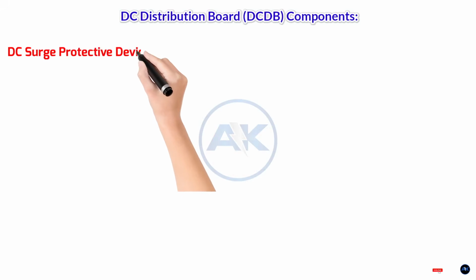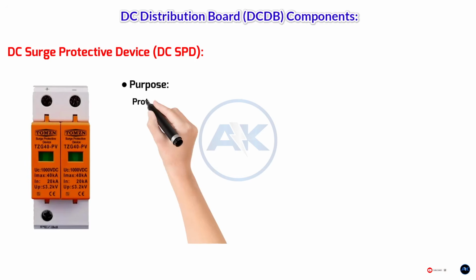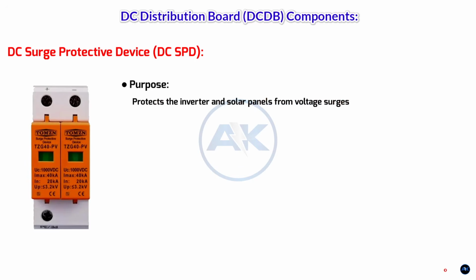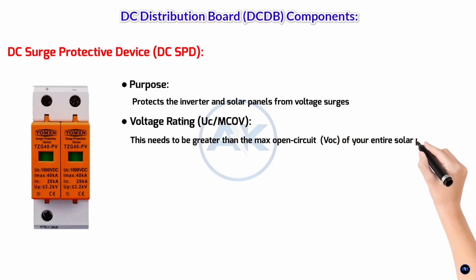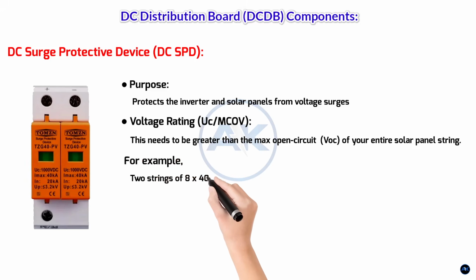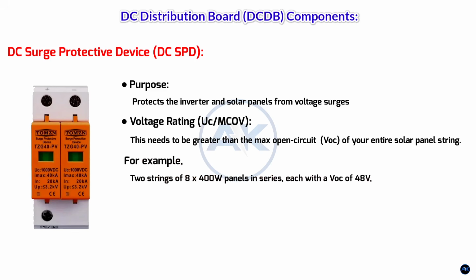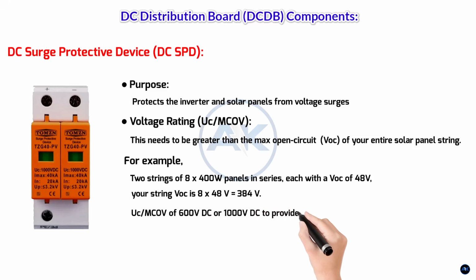DC surge protective device, DC SPD, purpose: protects the inverter and solar panels from voltage surges caused by lightning strikes or other electrical disturbances. Voltage rating, UC/MCOV. This needs to be greater than the maximum open circuit voltage, VOC, of your entire solar panel string. For example, if you have two strings of 8 times 400 watt panels in series, each with a VOC of 48 volts, your string VOC is 8 times 48 volts equals 384 volts. You would likely choose an SPD with a UC/MCOV of 600 volts DC or 1000 volts DC to provide sufficient headroom, as actual VOC can increase in colder temperatures.